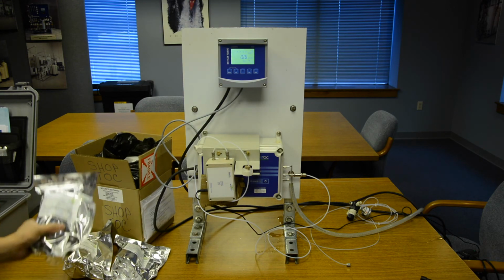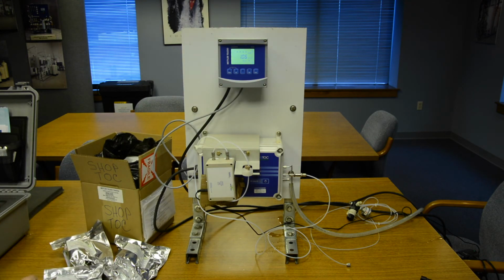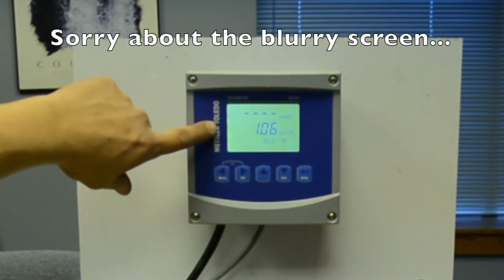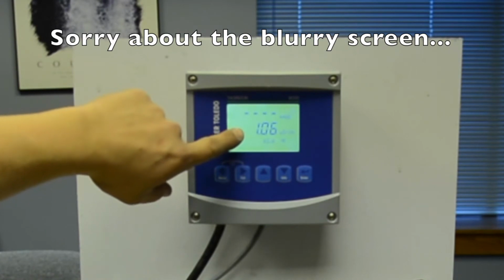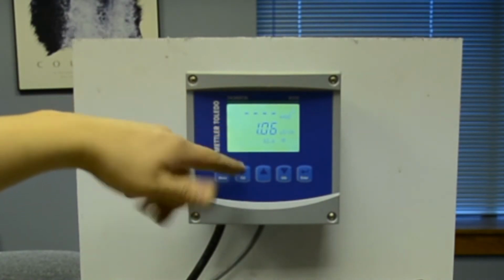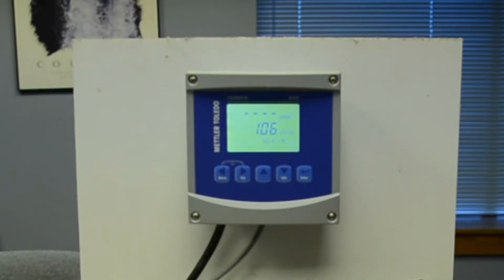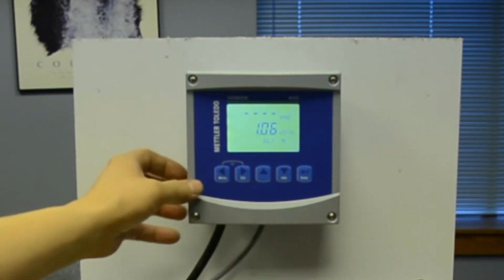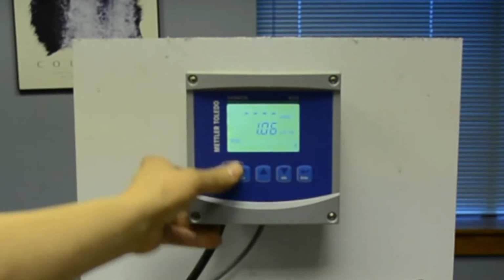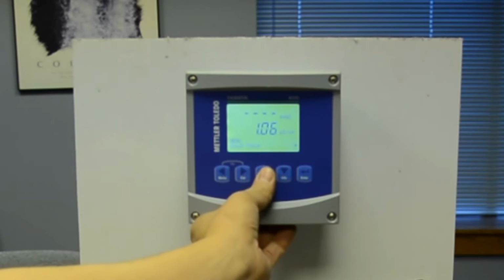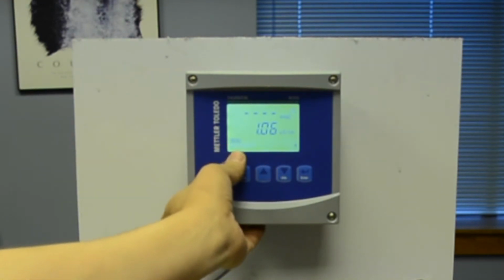You start off with the reagent water solution. Before performing this calibration though, you may need to reset up another channel on your M300 to show conductivity as opposed to resistivity or another measurement that may be located on it. To do this, go into your M300 and press menu. Then scroll down or up until you get to configure.